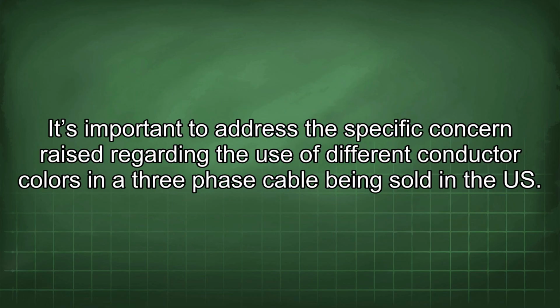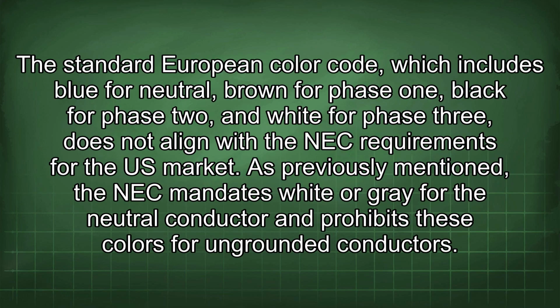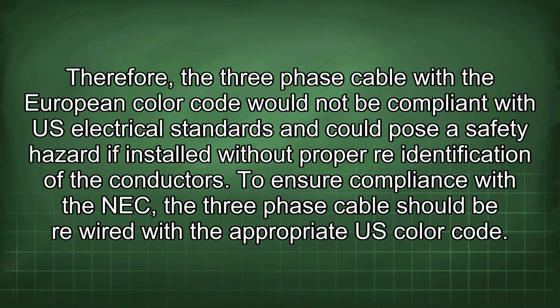It's important to address the specific concern raised regarding the use of different conductor colors in a 3-phase cable being sold in the US. The standard European color code, which includes blue for neutral, brown for phase 1, black for phase 2, and white for phase 3, does not align with the NEC requirements for the US market. As previously mentioned, the NEC mandates white or grey for the neutral conductor and prohibits these colours for ungrounded conductors. Therefore, the three-phase cable with the European colour code would not be compliant with the US electrical standards and could pose a safety hazard if installed without proper re-identification of the conductors.